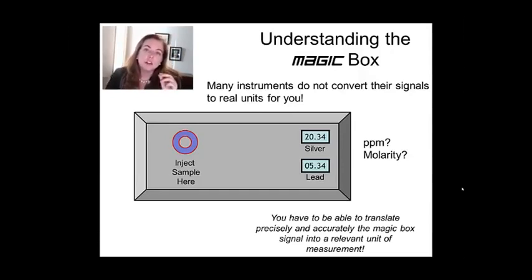It's putting known materials into our instrument of known concentrations, measuring the output signal, and from that creating a calibration curve that helps us understand, when we get any signal out of this instrument, what it means in terms of concentration of the material.